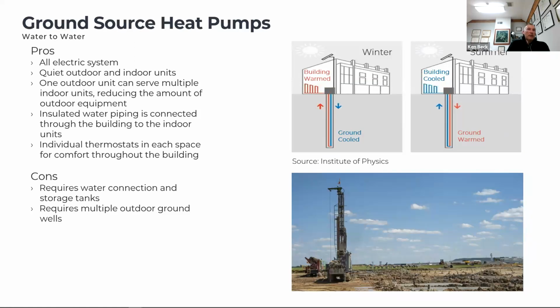Ground source heat pumps. So ground source heat pumps are using the natural temperature of the earth. So typically it's about 50 to 55 degrees. And New England's a perfect place for ground source heat pumps because we are able to disperse the heat in the winter and absorb the heat, you're able to offset the temperatures of the cooling season and the heating season so that you never overheat or overcool the ground surrounding the wells.